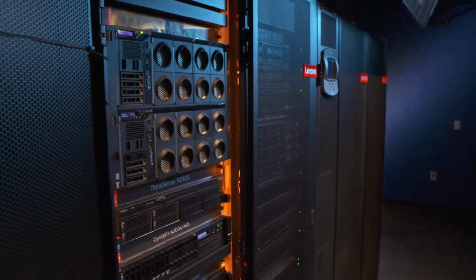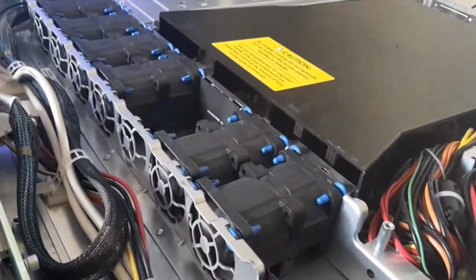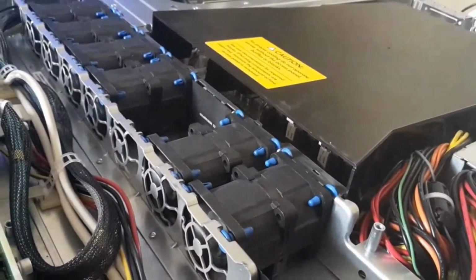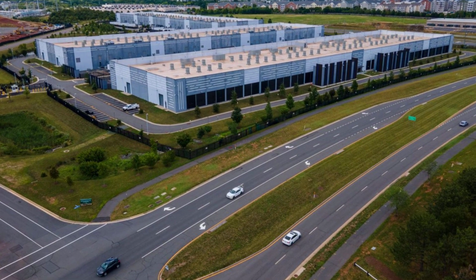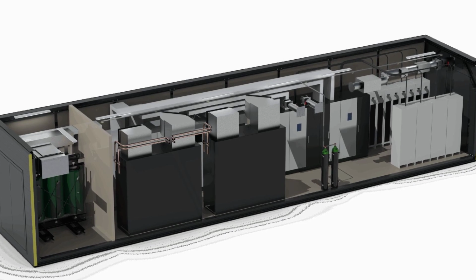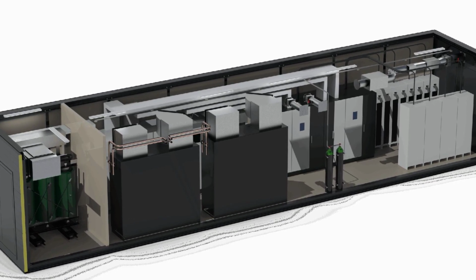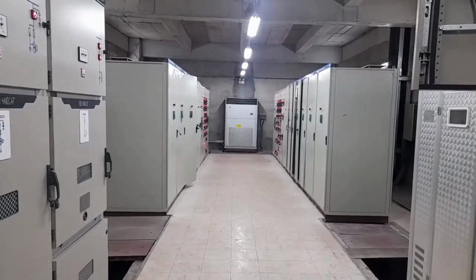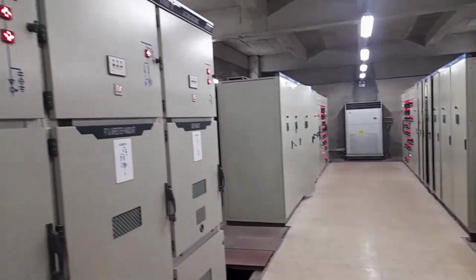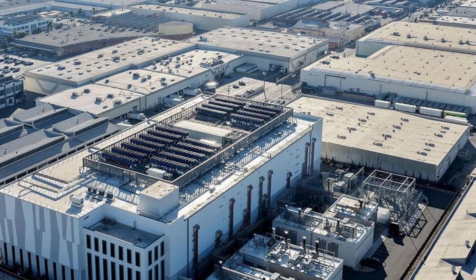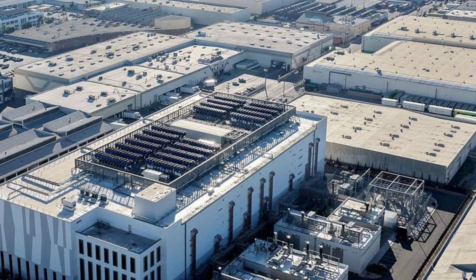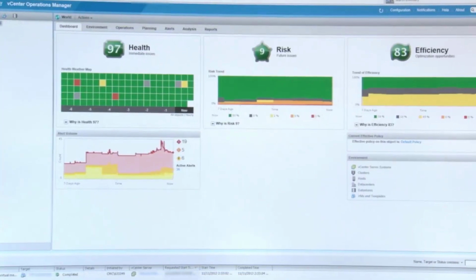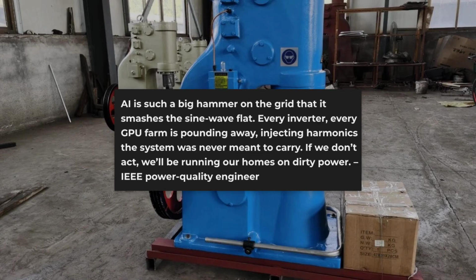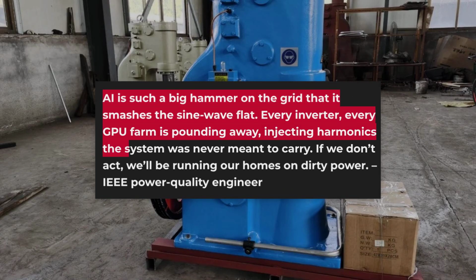The main source is nonlinear loads, machines that gulp power in sharp, uneven bursts. Data centers are the biggest offenders. Their switched mode power supplies, variable frequency drives, and uninterruptible power systems all chop and reshape electricity, injecting harmonics back into the grid. A single data center focused on AI can draw as much power as 10,000 homes, but its load is anything but smooth. As one IEEE engineer put it, AI is such a big hammer on the grid, it smashes the waveform flat.